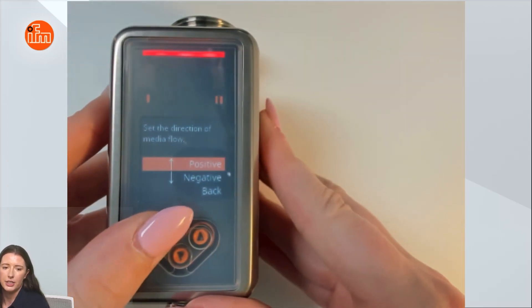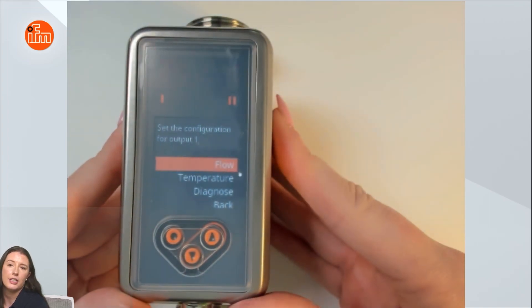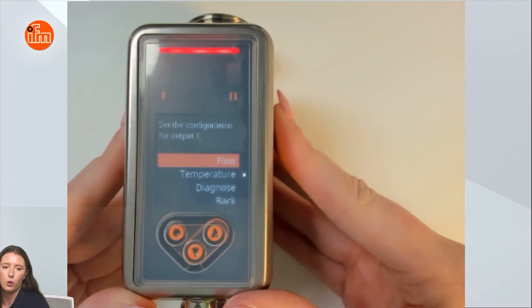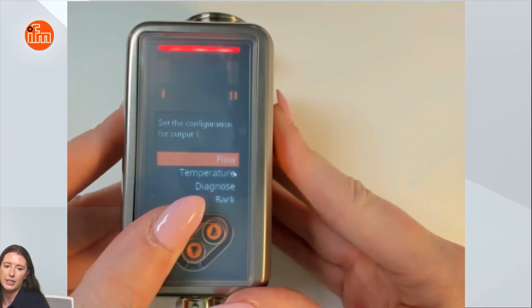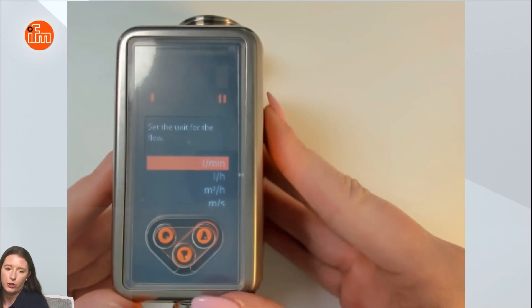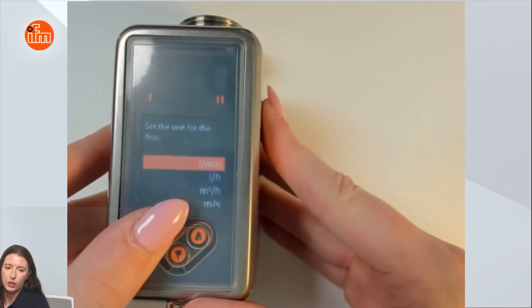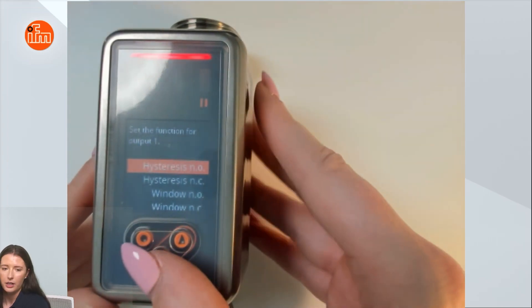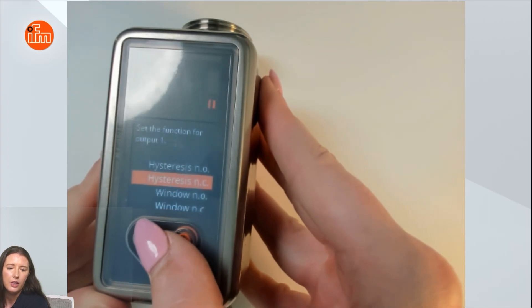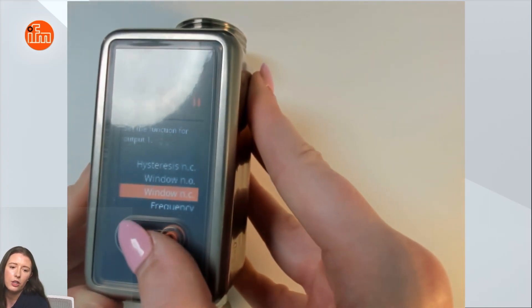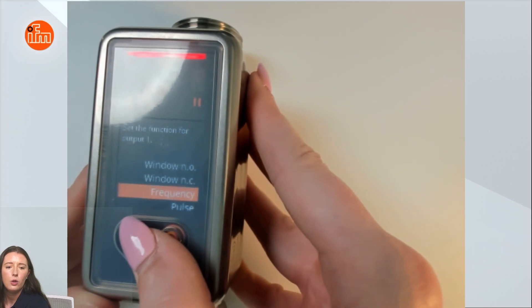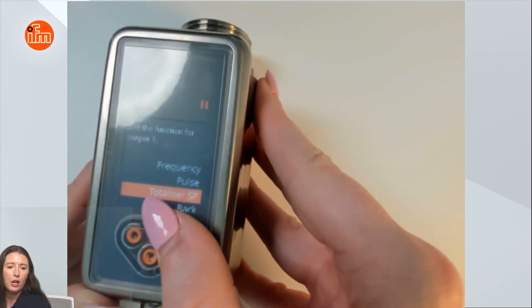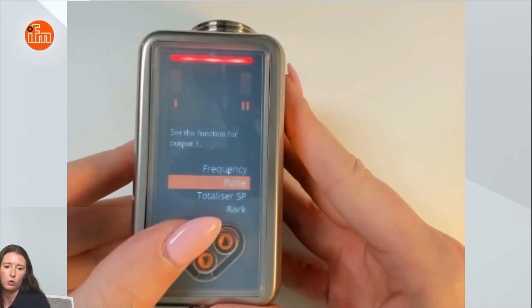Press enter to select that, and next it's going to ask you to set up each of your outputs. For output one you can decide to set it for flow, temperature, or diagnostics. I'm going to set it for flow, and then it's going to ask you for your units. I'm going to select liters per minute, and next it's going to ask you what you want your output to be: a hysteresis normally open or normally closed output, a window normally open or normally closed output, a frequency output, a pulsed output, or a totalizer set point. For this example I'm going to set it for a pulsed output to show you how to set up the totalizer.